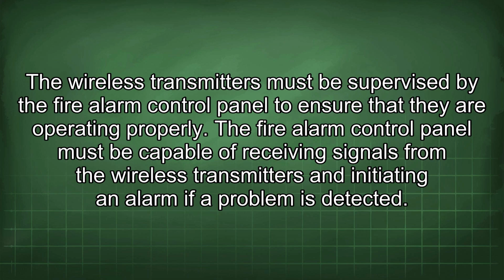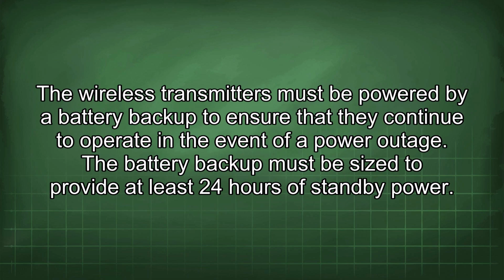The fire alarm control panel must be capable of receiving signals from the wireless transmitters and initiating an alarm if a problem is detected. The wireless transmitters must be powered by a battery backup to ensure that they continue to operate in the event of a power outage. The battery backup must be sized to provide at least 24 hours of standby power.